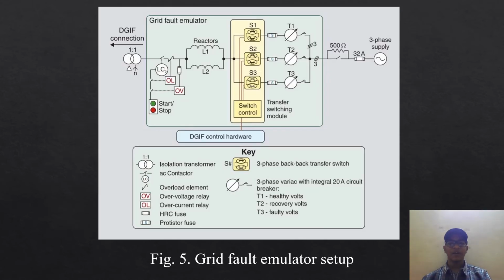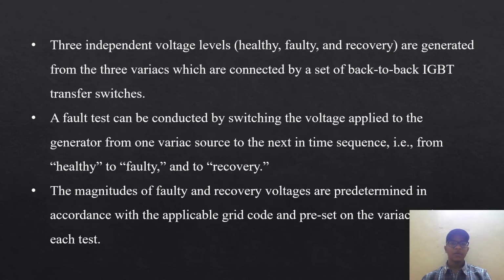Here is the grid fault emulator setup. Three independent voltage levels are generated from three variacs which are connected by a set of back-to-back IGBT transfer switches. The magnitudes of faulty and recovery voltages are predetermined in accordance with the applicable grid code and preset on the variacs for each test.